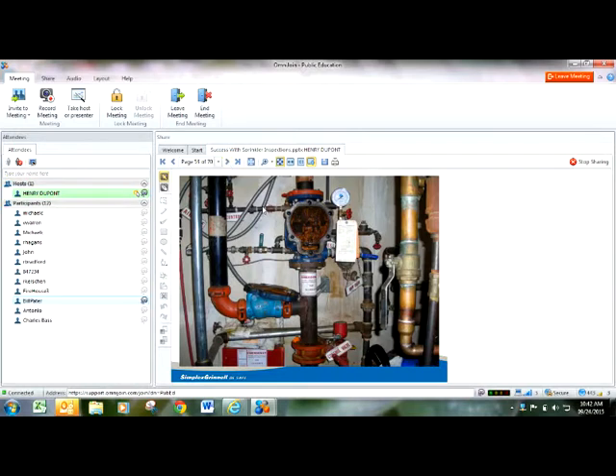Furthermore, a nitrogen generator will help dry out systems where you have improper pitch on your sprinkler piping and you just can't get the water out from condensation. Well, a nitrogen generator will absorb all that water, and it'll mitigate water and corrosion in the sprinkler system.